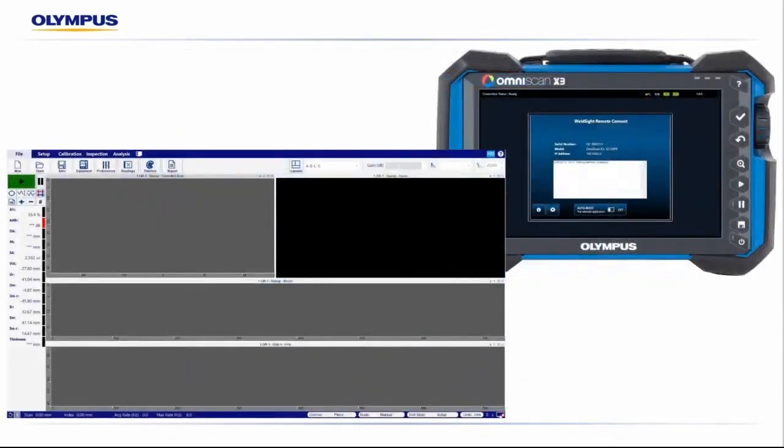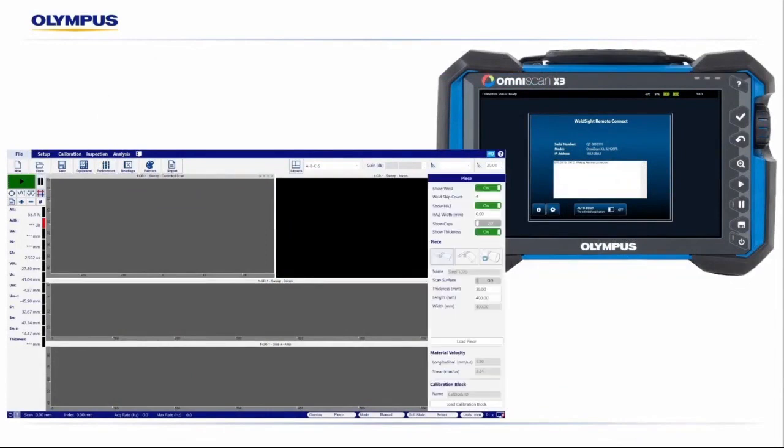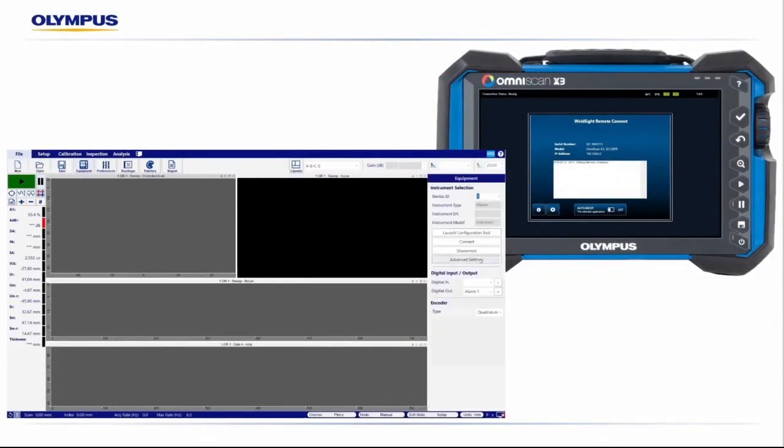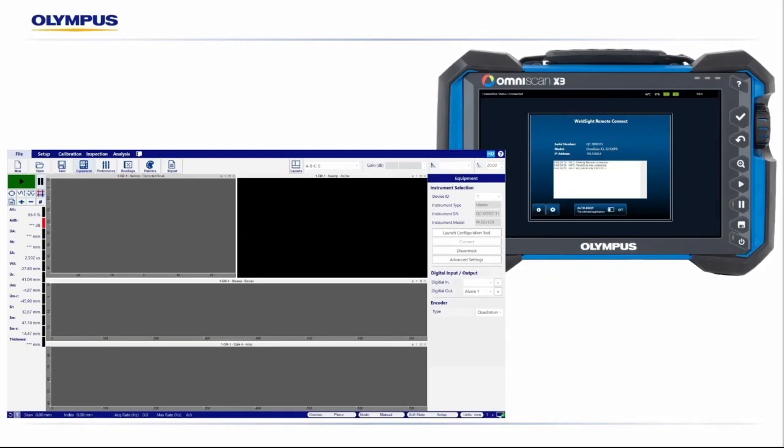If the software is already open, we simply click the System Utility icon on the bottom right corner. We'll select Connect, and then we'll see a visible green checkmark on the right-hand side showing that the OmniScan is connected. If the WeldSight software is not open and the WeldSight utility is launched first, once WeldSight loads, it'll automatically connect, and you're ready to start your data acquisition.